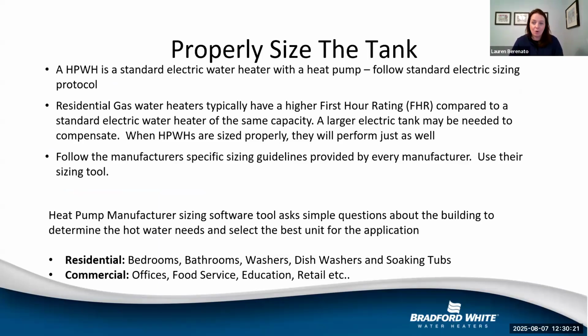Now, one of the things too about heat pump water heaters is that you really need to make sure you're properly sizing your tank. So with this, a heat pump water heater is a standard electric water heater with a heat pump. Residential gas water heaters typically have a higher first hour rating compared to the electric water heater, and therefore a larger electric tank may be needed to compensate. When heat pumps are designed properly, they will perform just as well. But if they are not sized properly, you're going to have a challenge making sure that you have that hot water demand being met. I mentioned this at the start of my presentation, but you really want to follow the manufacturer's specific sizing guidelines. Every manufacturer will be different, but really keep a close eye on that.